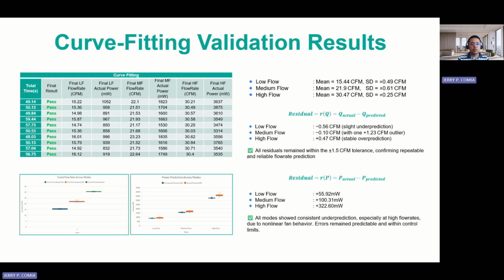For flow rate residuals, low flow had negative 0.56 CFM, medium flow had negative 0.1 CFM, and high flow had positive 0.47 CFM. All of these values were within the plus minus 1.5 CFM tolerance band. This confirms that the curve fitting method produces repeatable and reliable airflow prediction across all three operating modes.